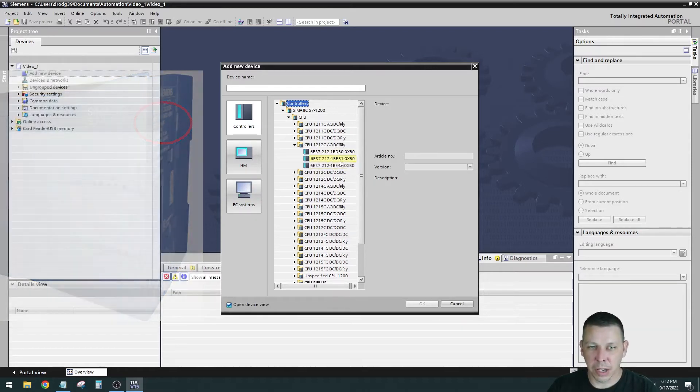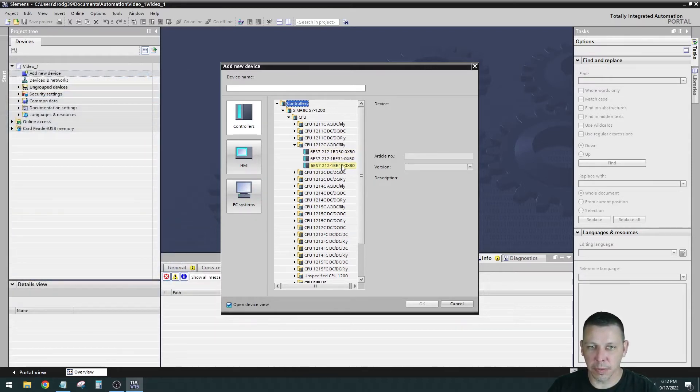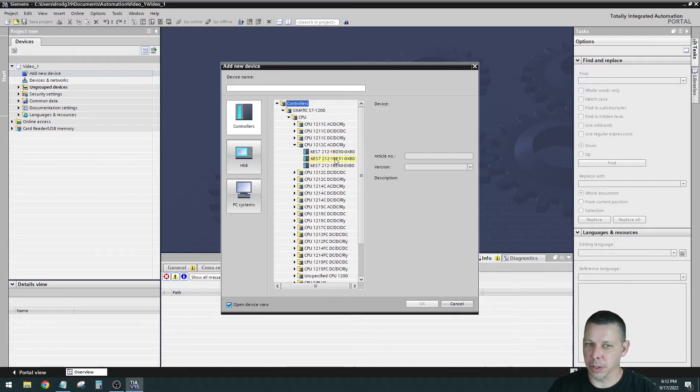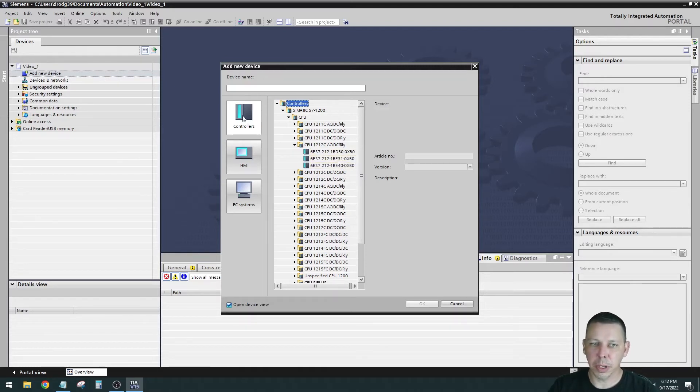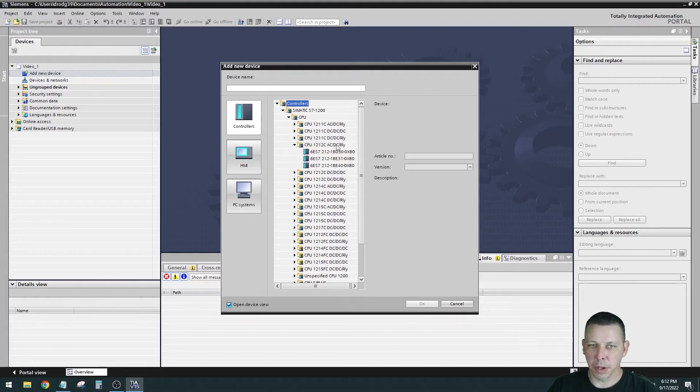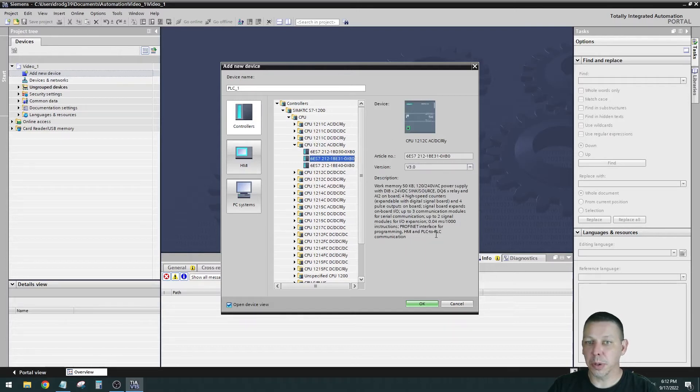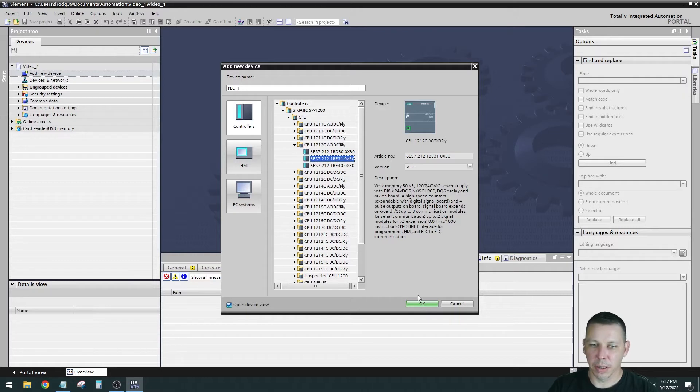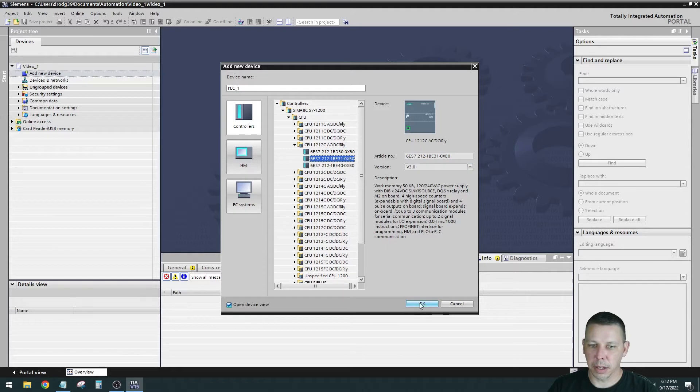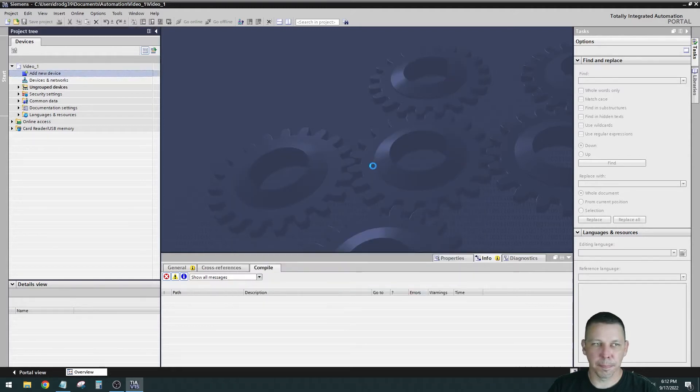This is the firmware revision and you'll find that on the side. I'll drop a picture on what that looks like and where you can find that number. They're almost identical except for this 30, 31, and 40 right there. It's pretty small print on the side of the processor where you'll see which firmware revision you have. I'm pretty sure mine's the middle one but we'll find out when we try to go online. It'll say that it is the wrong hardware if it's not the right one.